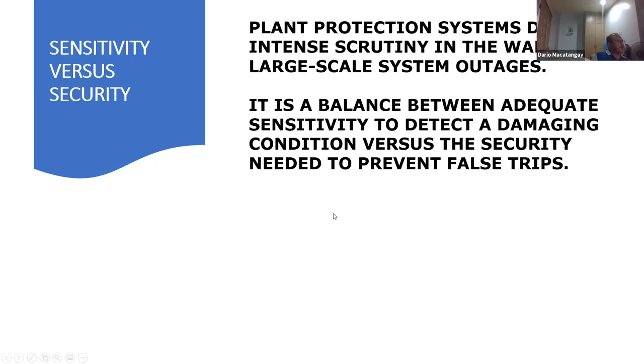All right. So, sensitivity versus security. In terms of protection, we have to balance sensitivity and security. What I mean by sensitivity is the ability of the protection to sense the current and actually isolate the defective system promptly. That's sensitivity. Now, security means that you should not trip the generator when it's not needed to trip. For example, with protection coordination, the transformer needs to trip, but the generator does not need to trip. That is part of the security issue that needs to be considered. So when we're doing systems analysis, we want to see the effect on the system, as well as the balance between sensitivity and security.